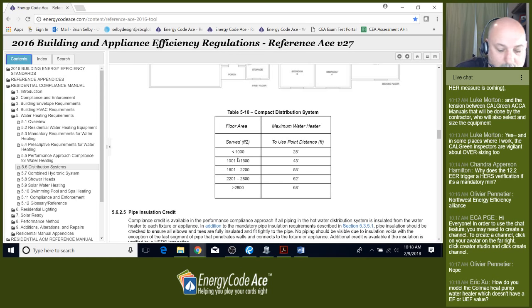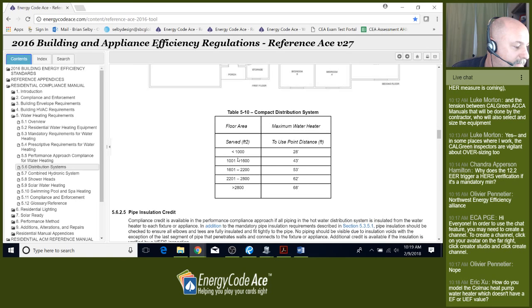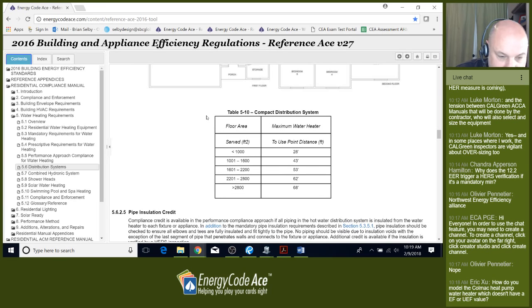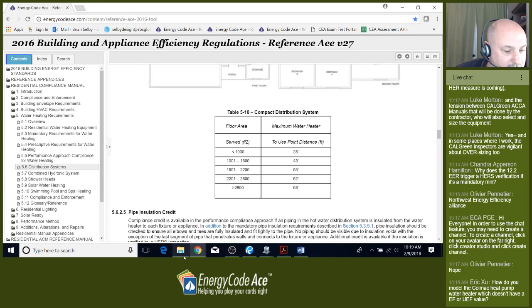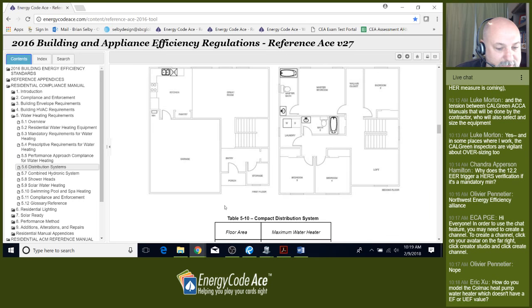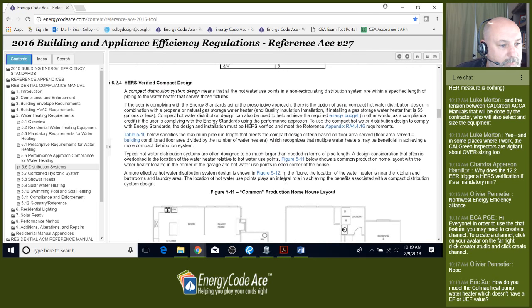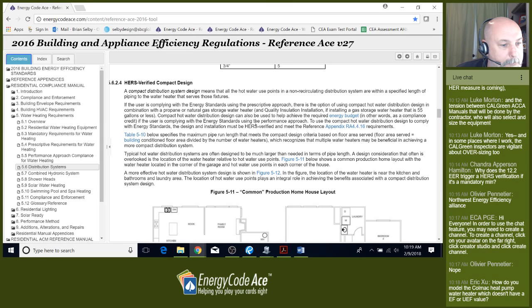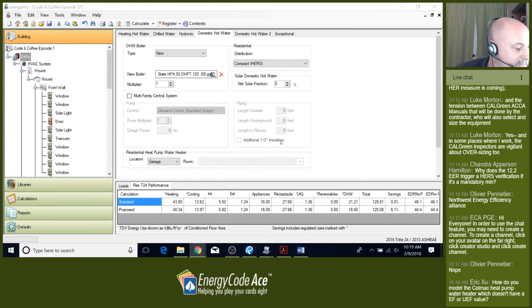From the source — probably in the garage — to the farthest point, the linear dimension is 45 feet. We're within our 53-foot maximum run. We just need HERS verification and we're good to go. Back in Energy Pro, we'll check the compact HERS distribution. Does anybody have any predictions on whether we're going to comply? We've switched from a 92 AFUE furnace, 14 SEER / 11.7 EER air conditioner, and a tankless water heater at about 95 energy factor, to all electric. Any guesses?